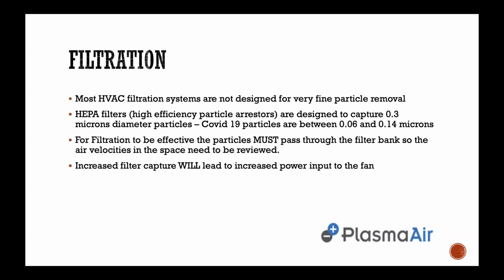The most important factor is that most HEPA filter systems - and we can see very clearly on this slide the actual size of the virus - a HEPA filter is designed to capture about 0.3 micron diameter particles, and COVID-19 particles are between 0.06 and 0.14 microns. So we have to question ourselves, are HEPA filters really an answer in the first place? And with the increased power input we'd have to put into the system, is it an economic and viable solution?